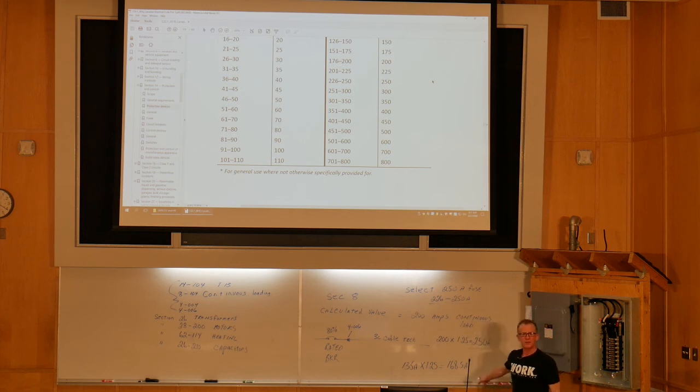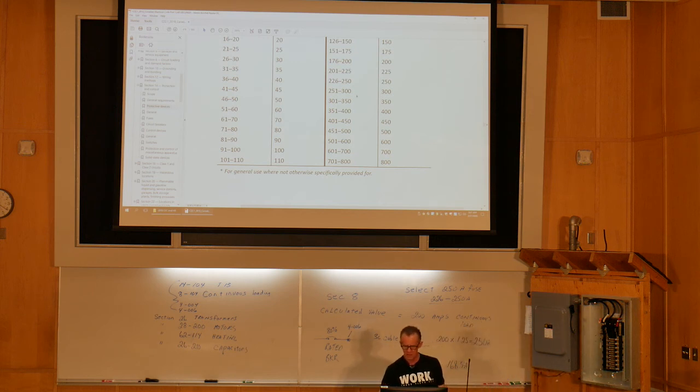That comes out to 168.5 amps. So that's the minimum ampacity of the wire and the fuse. Now, that just so happened to fall right onto the ampacity of a fuse, so you could go to Table 13 and select it. But here, there is no 160 amp fuse, or 168. We must go to the next available one, which, if we look in the table, is 175.